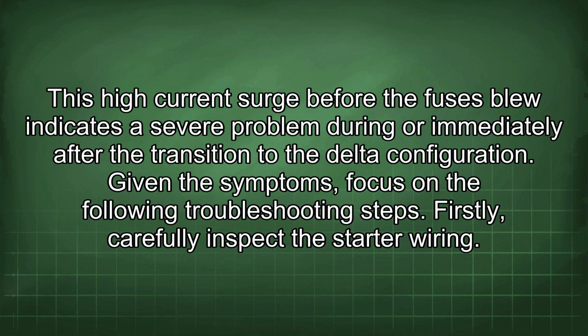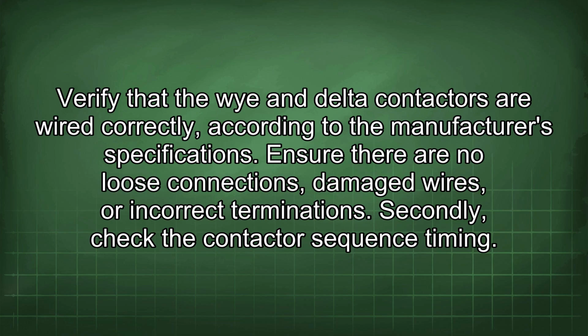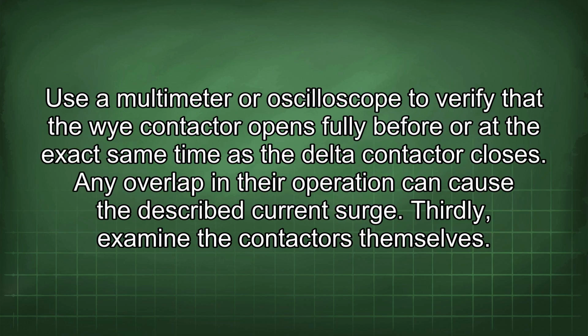Given the symptoms, focus on the following troubleshooting steps. Firstly, carefully inspect the starter wiring. Verify that the Y and delta contactors are wired correctly according to the manufacturer's specifications. Ensure there are no loose connections, damaged wires, or incorrect terminations. Secondly, check the contactor sequence timing. Use a multimeter or oscilloscope to verify that the Y contactor opens fully before or at the exact same time as the delta contactor closes. Any overlap in their operation can cause the described current surge.